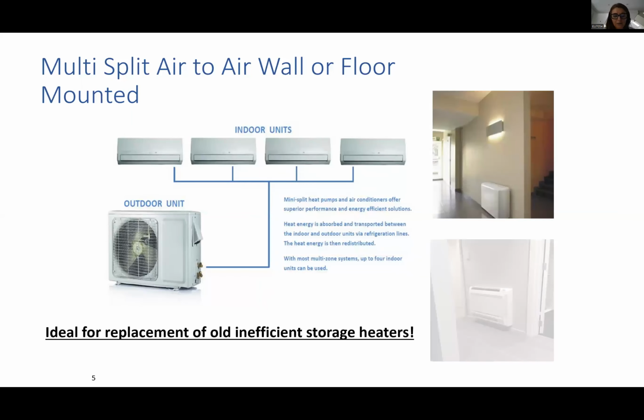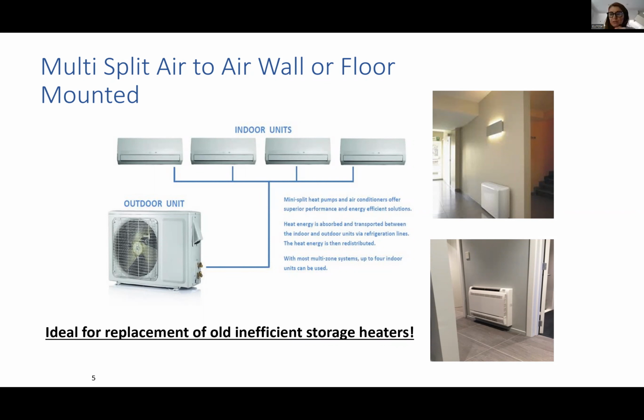Technology letting me down. Okay, so the next type of system is an air-to-air system. Ordinarily, this would have been used in Ireland in retail. They're used to cool comms rooms. They're used in offices for heating and cooling. A fantastic system for any type of building that has intermittent use. Believe it or not, funeral homes are actually a type of building that use this technology because they're intermittent use. You don't necessarily know when the building will require heat. So for instant heat, these are fantastic.